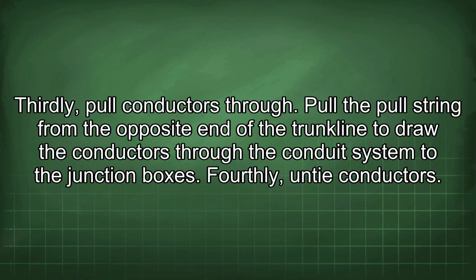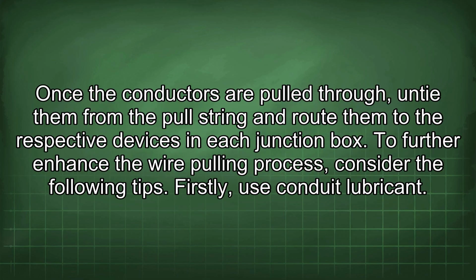Thirdly, pull conductors through. Pull the pull string from the opposite end of the trunk line to draw the conductors through the conduit system to the junction boxes. Fourthly, untie conductors. Once the conductors are pulled through, untie them from the pull string and route them to the respective devices in each junction box.